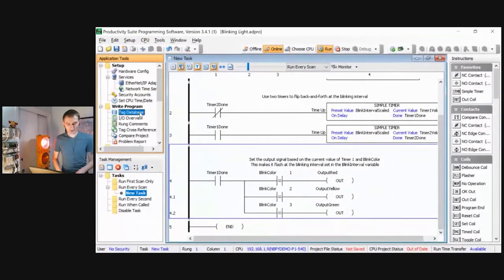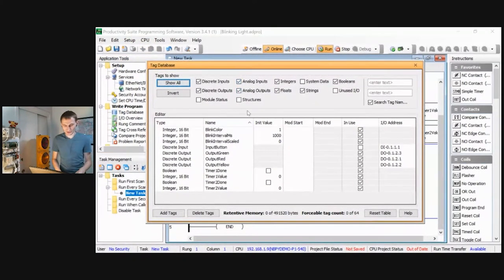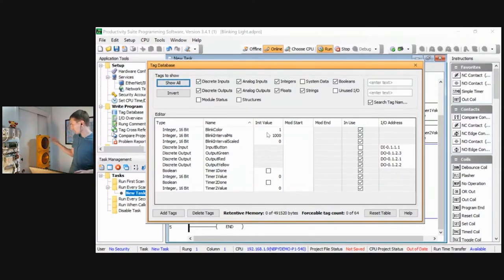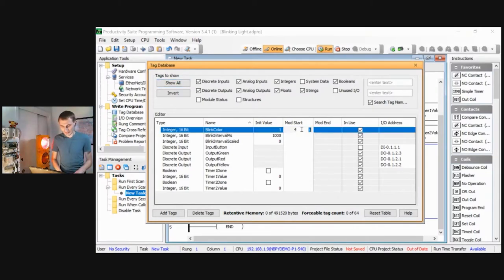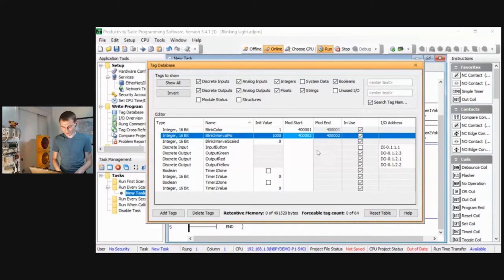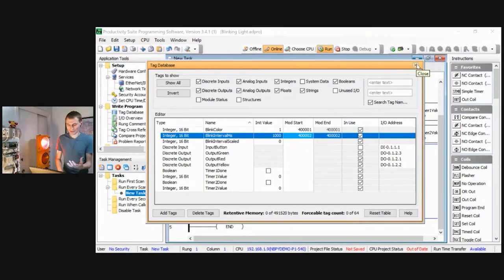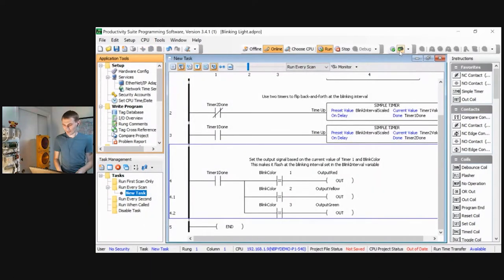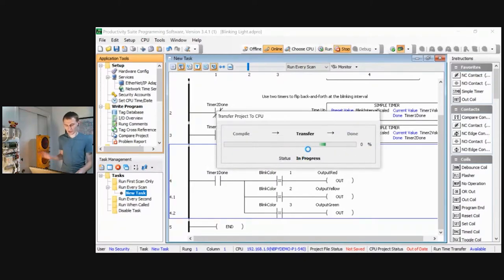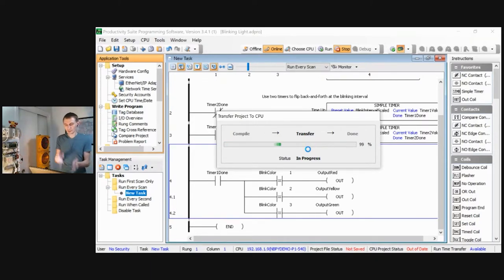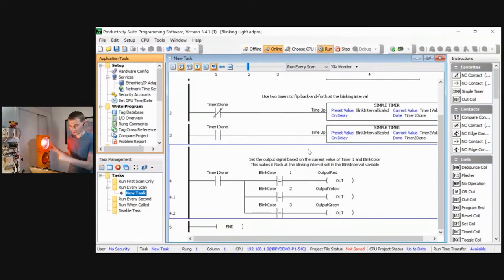The PLC has a convenient list of all variables used. Blink_color and blink_interval_millisecond are right at the top with default values of 1 (blinking red) and 1000 (one second on, one second off). I'm going in to assign those Modbus register addresses. After configuring it, I stop the PLC, reprogram it to share these variables with the network, and when it's done it starts blinking again.